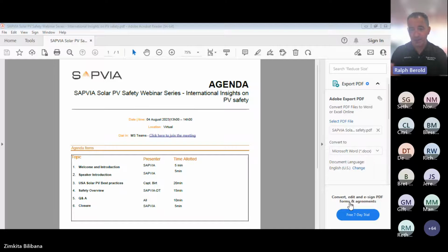Then we said to the homeowners and to the insurance companies, listen, now we can control that high voltage DC. We can take the voltage down to 60 volts DC from the panel. We've eliminated the MC4 connectors and the connections to a high voltage inverter by replacing with 230, 50 hertz. And we've got a system that has built-in rapid shutdown. How does that work? Each microinverter, if there are any faults in the system, what you're looking at is a complete rapid shutdown to modular level.